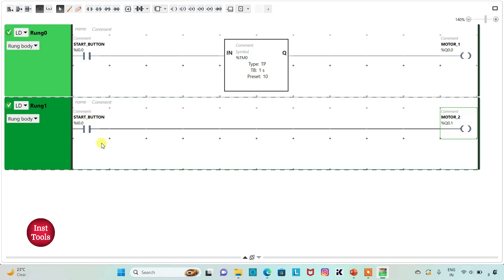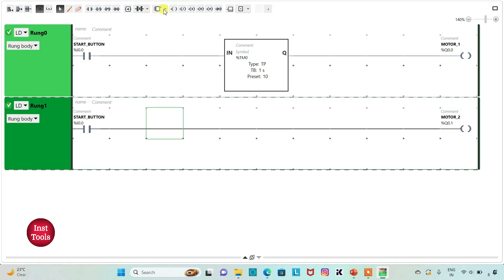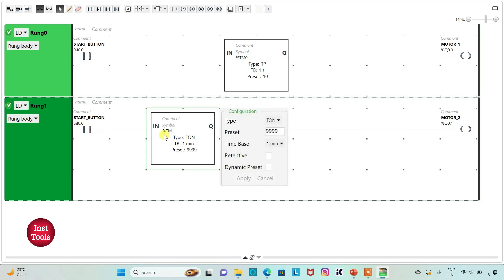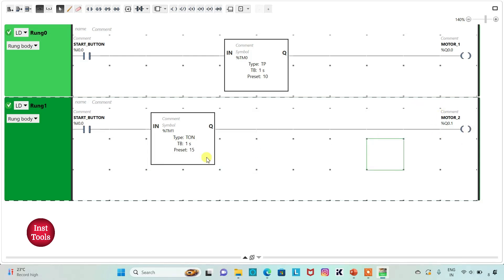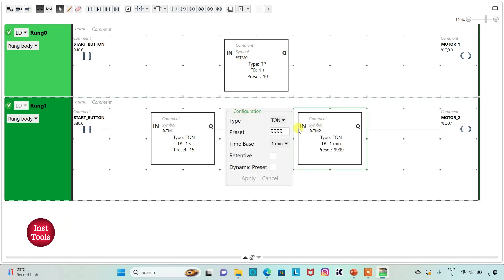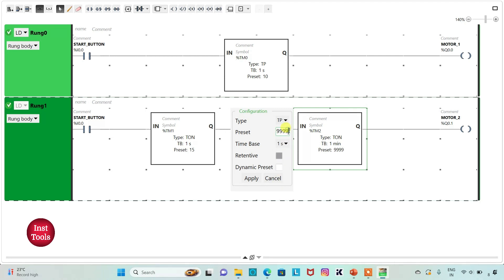When I turn on the start button, motor 2 will be on after 15 seconds. So I will insert a timer here and it should be TON because we have to delay. I will change the time base to 1 second and preset value as 15, then Apply. Motor 2 should also be on for 20 seconds, so I will insert another timer for motor 2 and it should be TP. I will change the time base to 1 second and preset value as 20.